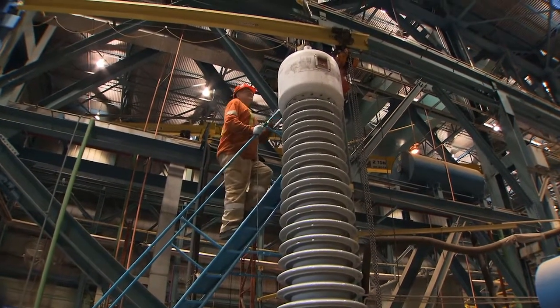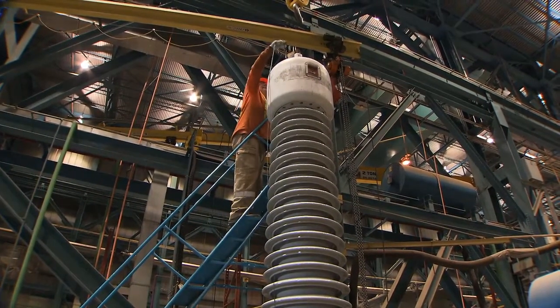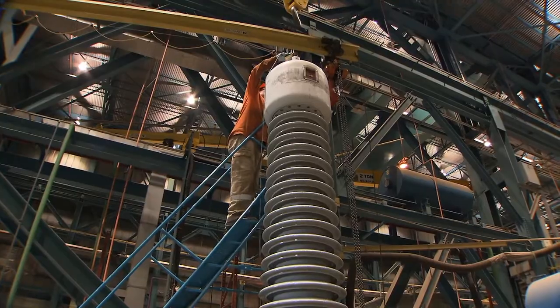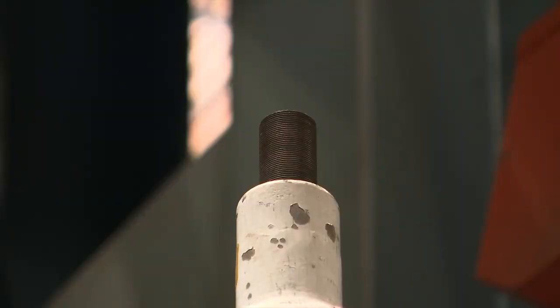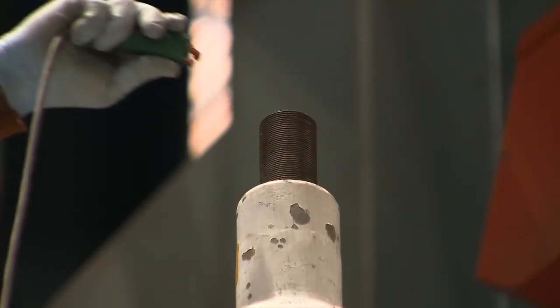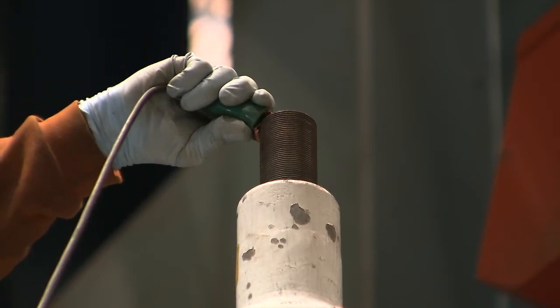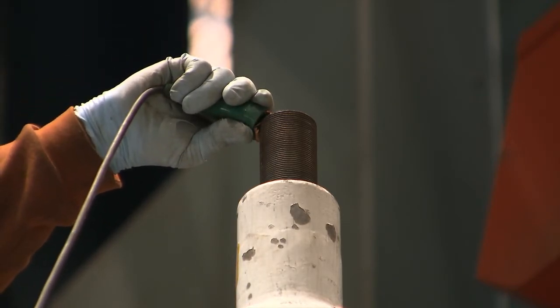Using the rolling warehouse ladder equipped with handrails and with the locking mechanism activated, climb to the top of the bushing to the level of the terminal. Connect the cable extension to the threaded rod extending out from the top of the terminal on the bushing.